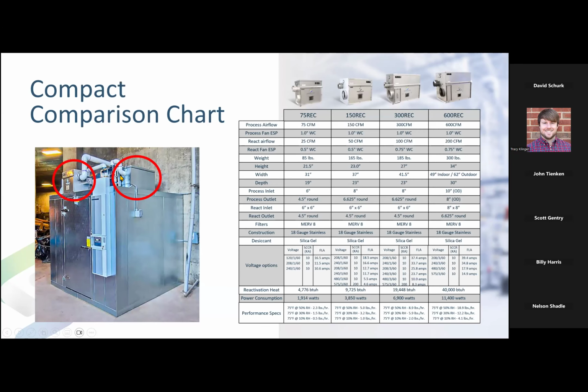This shows an example of a couple of, I think, 75 CFM compact units provided on a freezer storage facility. So let's think about this for a minute. Let's say this is being maintained at, I don't know, 0 degrees Fahrenheit. It doesn't really matter. And you've got some type of refrigeration evaporator in here that's attempting to maintain 0 degrees Fahrenheit. What happens every time you open this door to go in and get something out? This warm, super moist air will rush in and it will hit those cold surfaces and it will immediately turn to frost. It will do what's called deposition. It will go from a vapor to a solid without condensing.